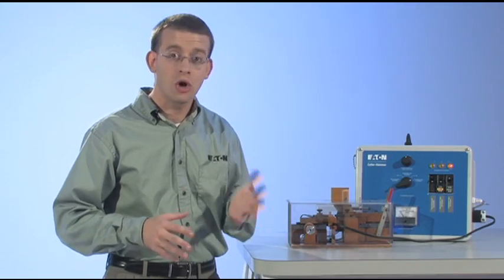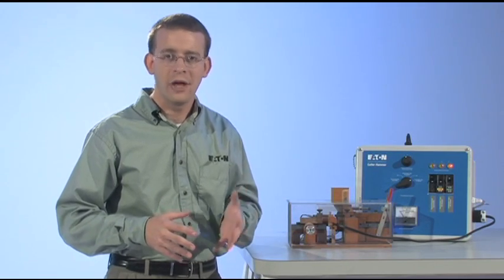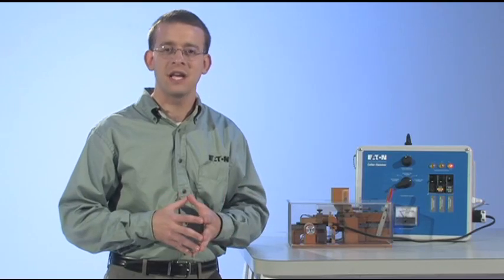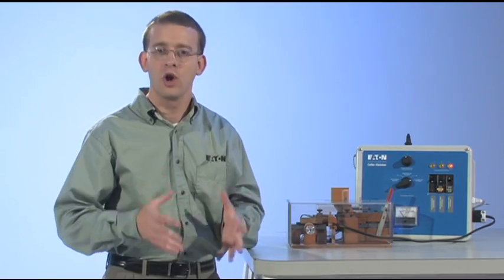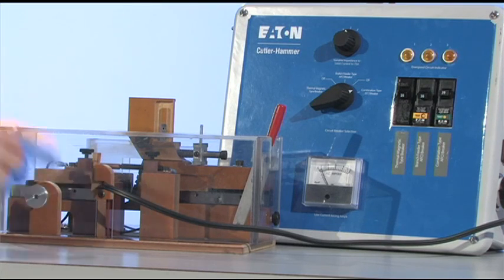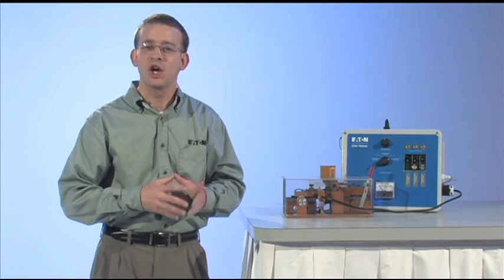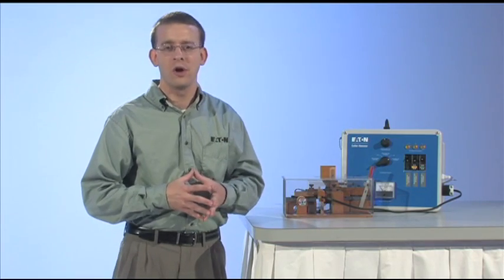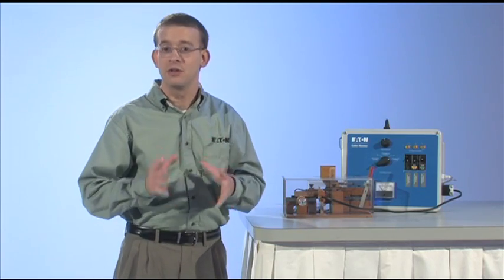The combo AFCI was developed to detect this low current arcing. In addition to short circuit, overload, and high current arc fault protection, the combo AFCI provides protection for low current arc faults. As we see, the combo AFCI is able to detect this low current arc fault where any other breaker would fail to respond.